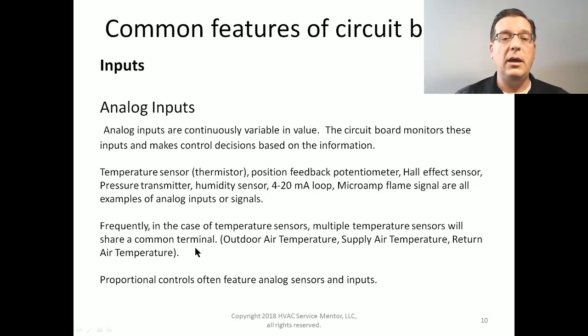Okay. Frequently, in the cases of temperature sensors, multiple temperature sensors will often share a common terminal. So, for example, if we have a residential zoning control system, you may have an outdoor air temperature sensor, a supply air temperature sensor, and a return air temperature sensor. And there will be a total of 4 terminals that these will land on. There will be the OA terminal, the SA terminal, the RA terminal, and the C terminal.